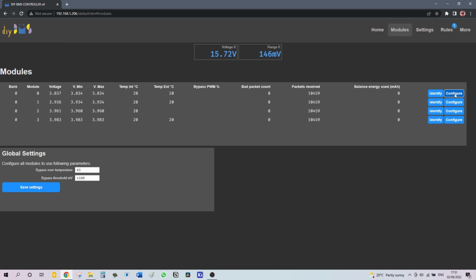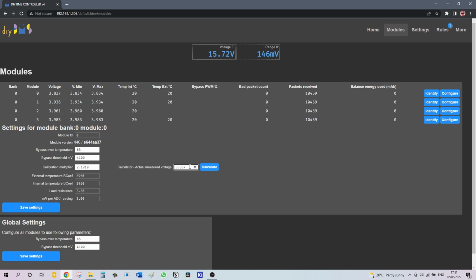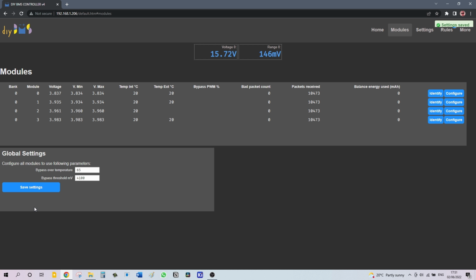So I'll go to configure, and this one shows 3.837. I'll put 3.84, calculate, and it calculates the calibration multiplier. Now we can save the settings.